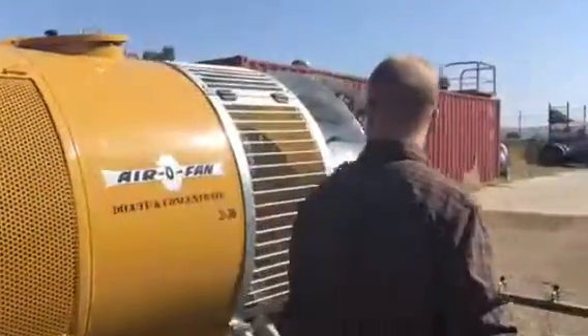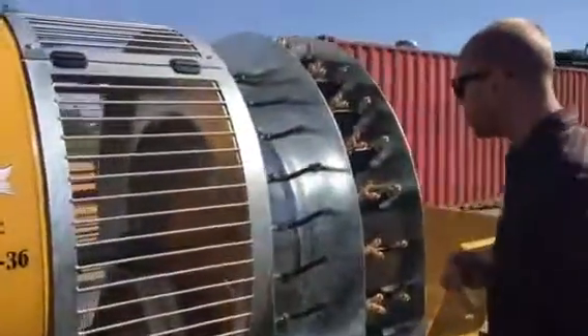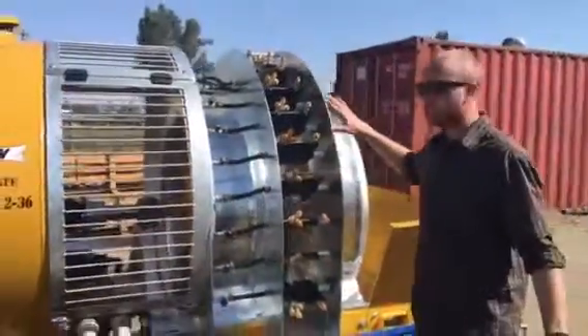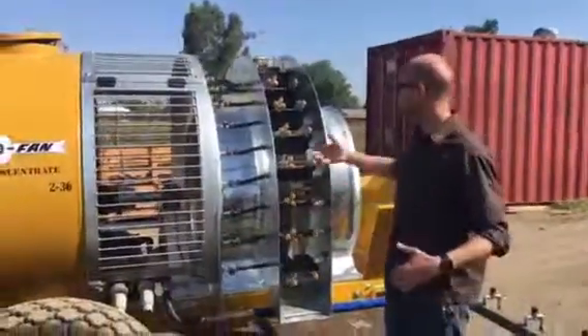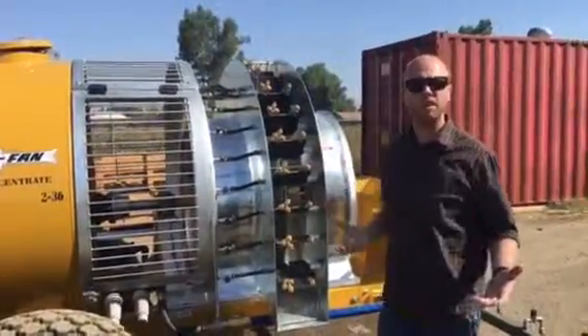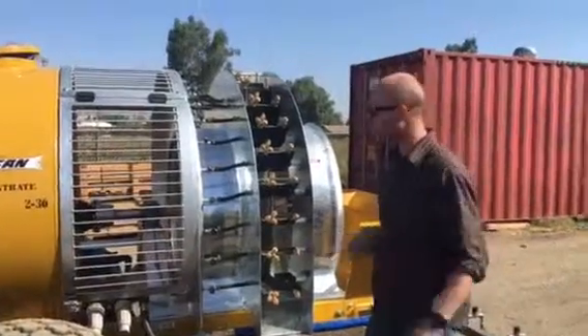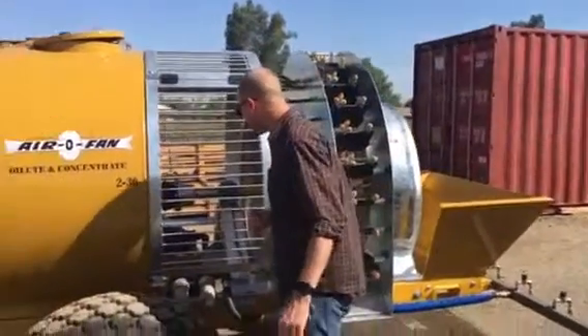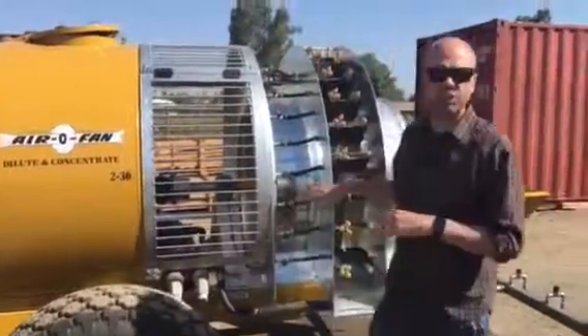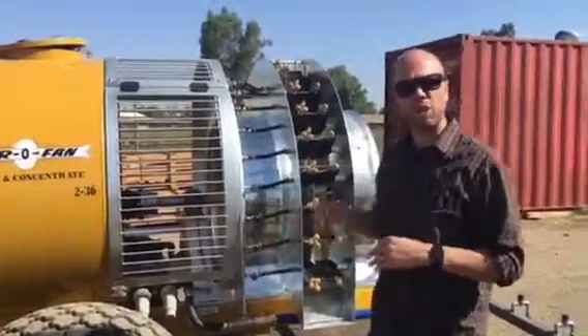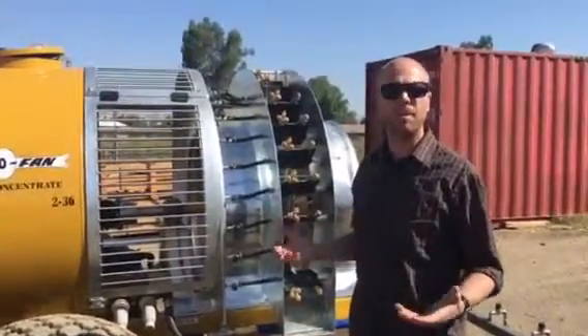Going to the back of the machine, debris on the fans, debris within the air vanes. You just want to make sure that you physically inspect that and clean those. This particular machine, because of its nature, doesn't have a mechanical agitator, so you don't have to have any mechanical agitation to maintain.